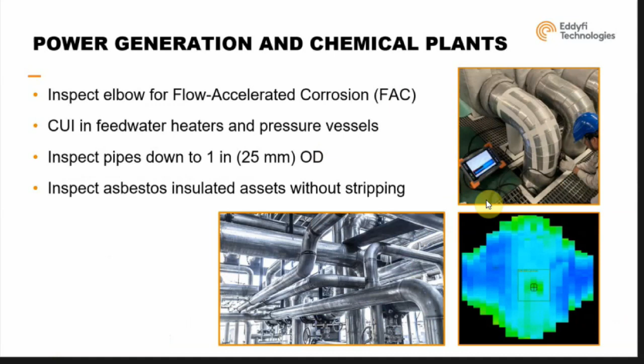Elbows is a geometry that was also difficult to address, so now you can do elbow inspection with PEC. Galvanized steel is ferritic and ferromagnetic, which brings an additional challenge to pulse eddy current use. To address this challenge, we have made a specific probe, the galvanized steel probe. This probe has a strong magnet embedded in it, so the probe will stick to the weather jacket made of galvanized steel and saturate the weather jacket, allowing the pulse to go through the jacket with less interference and less noise.